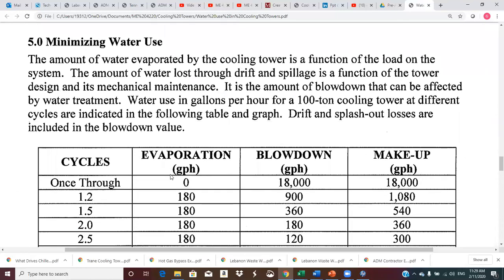So the amount of water evaporated by the cooling tower is a function of the load on the system. Water loss through drift and spillage is a function of the tower design and how it's operating. It is the amount of blowdown that can be affected by water treatment. So if we clean up the water better, then we don't have to blow down so much. So if we purify it more, or put more additives in there to keep, say, bacteria or mineral concentration down, then we don't have to blow down so much.